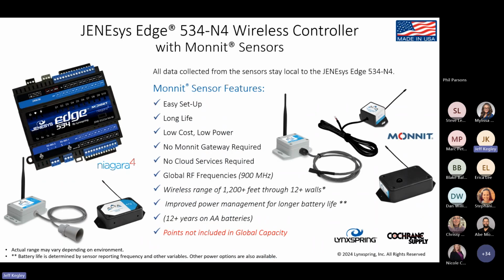We've expanded the capabilities of the 534 to meet our customers' needs. One thing our customers wanted was a wireless solution, and we found they liked Monnit predominantly, so we teamed up with Monnit. On the motherboard we put the Monnit radio, so the controller doesn't have to change size—it's not any bigger, it's the same size. We were just able to put the Monnit radio on the controller itself. Now you have the data from the wireless devices coming directly into Niagara, and if you're familiar with Monnit, this allows you to bypass sending it to the cloud and paying a fee for Monnit to store it. So it goes directly into Niagara from the sensor.